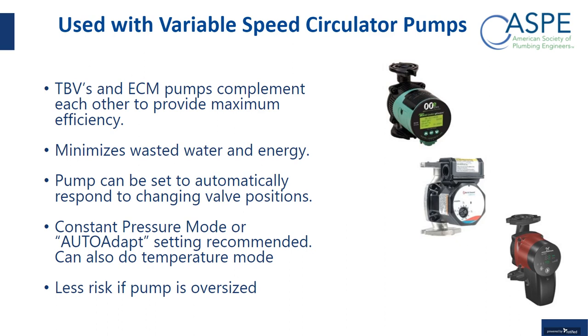The nice thing about thermostatic balancing valves versus, again, manual or pressure independent is that they work really well with ECM type pumps. You have two dynamic devices. You have the thermostatic valve, which is basically opening and closing based on temperature. And then you have the ECM or variable speed pumps that have different types of controls associated with them. What is used for the most part with thermostatic balancing valves and these types of pumps is putting them generally in a constant pressure mode.